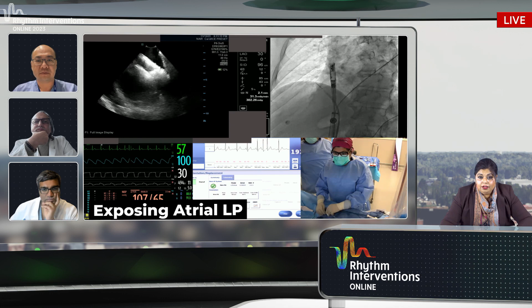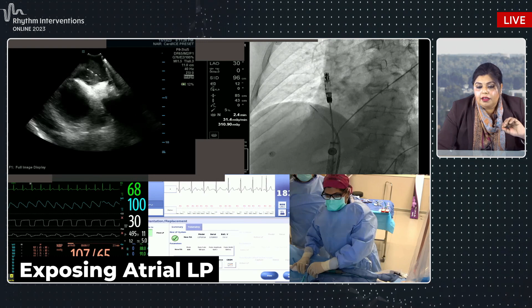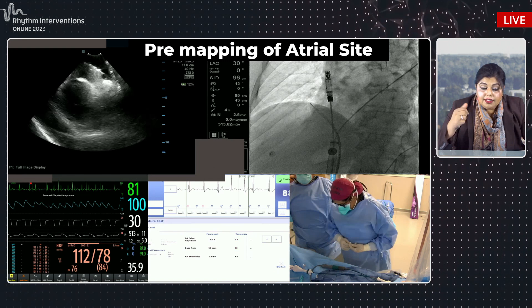So at this point, I'm actually exposing the device, pulling that protective sleeve all the way back, exposing the device. And this gives me the opportunity to map where I'm at. And to me, this is one of the characteristics of the Aveir device, having that pre-mapping capability, knowing the quality of the tissue that you're in contact with, and knowing probably the amount of contact you're in. And here you can actually do a current of injury. You can get a P-wave, and you can get your impedance, and you can even get a threshold.